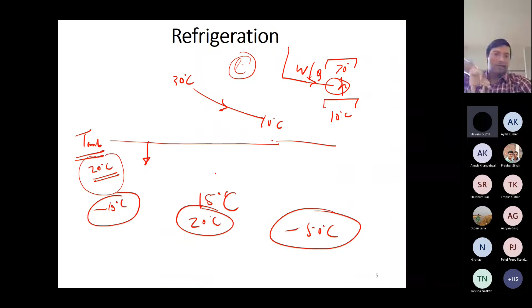Okay, so you want to keep your vegetables at 5 degrees C when your ambient is at -50. It is still a refrigeration system. It is just that the indoor and the outdoor unit will have to be reversed. Or think of your room also. You want to still maintain, let's say, 15 or 20 degree room temperature when your outdoor is at -50. Still the system is a refrigeration system. It is just that imagine the outdoor unit for your AC has become the indoor one, and the indoor unit has become the outdoor. That's it.